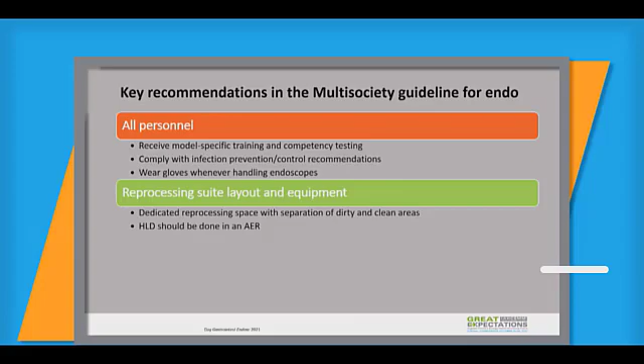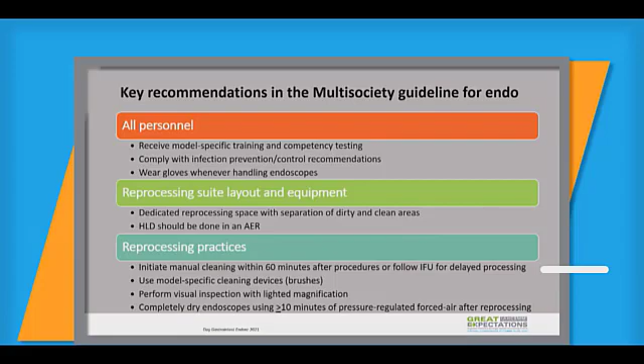But here's the doozy. It says that manual cleaning must be initiated within 60 minutes of the procedure, or you have to follow the manufacturer's instructions for delayed reprocessing, which generally involves extended soaking and extra scrubbing. It also says you should use model-specific brushes for lumens, so no more using one type of brush for all the scopes. And it says you should be doing visual inspection with lighted magnification for every scope every time.